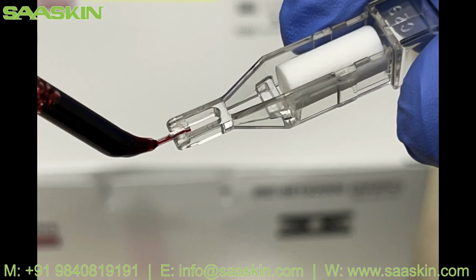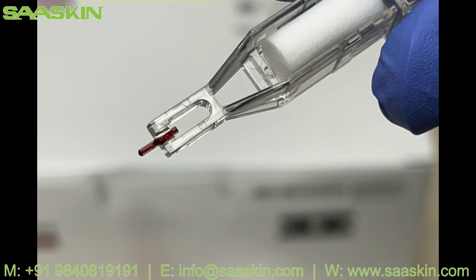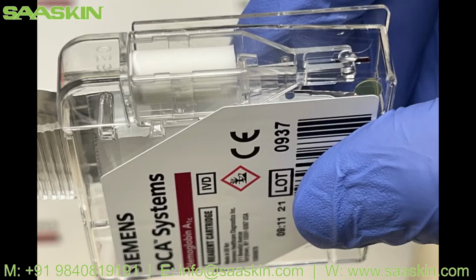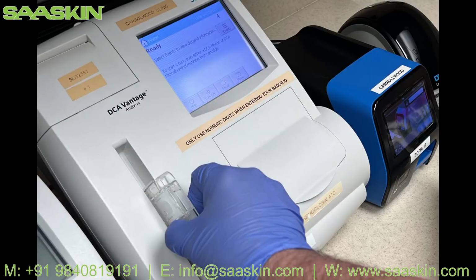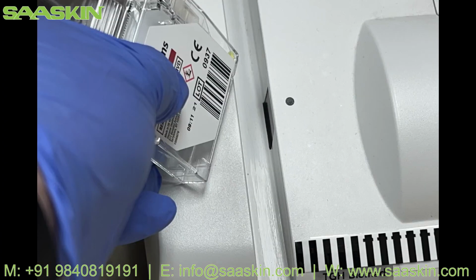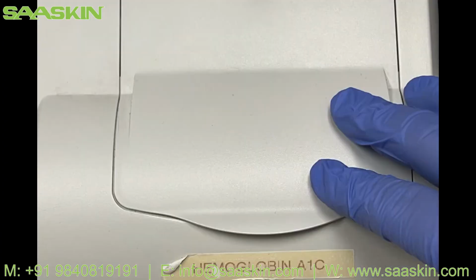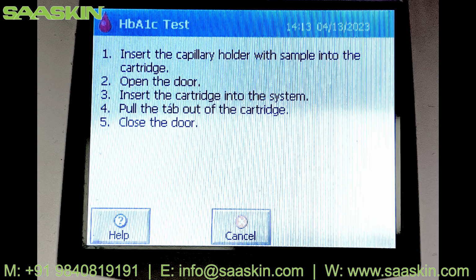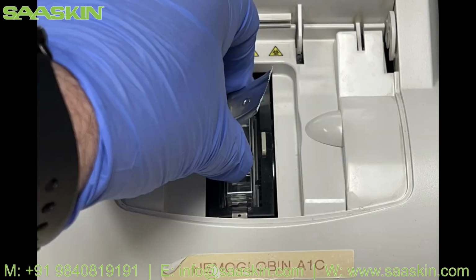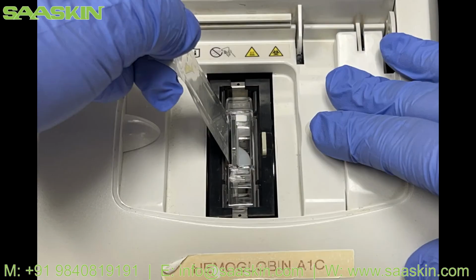Apply abnormal control sample to capillary collection device. Make sure there is no gap or overflow in the capillary device. Insert capillary collection device into the cartridge. Slide the cartridge in the bay for scanning. With the barcode facing the reader, open the meter door. The meter will instruct to insert the cartridge in the system until click. Then pull the foil tab out.